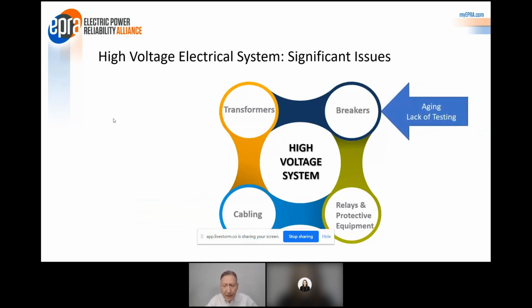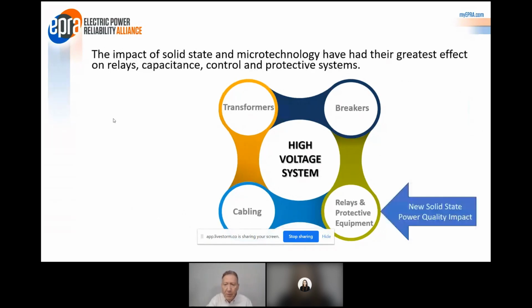The breakers, again, suffer from aging and lack of testing. There are protocols on breakers. We've got a lot of new gas breakers in the marketplace, and even those SF6 gas breakers are now becoming obsolete because the EPA doesn't like it. We're coming up with new gases that are much more inert, and IEEE is doing some standards work on that as we speak. But breakers suffer some of the same problems.